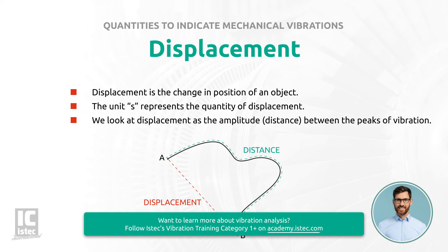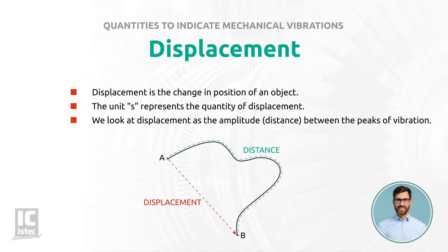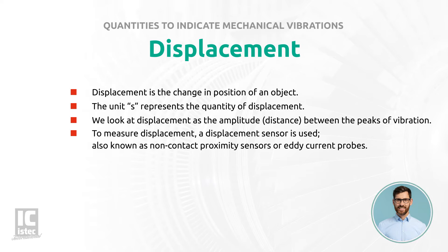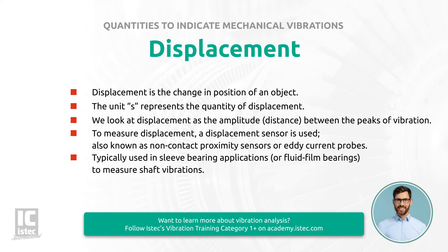We can see that both can be seen as a route from A to B, yet the distance is dependent on the route taken, whereas displacement is not. To measure vibration based on the displacement quantity, a displacement sensor is used. These sensors are also known as non-contact proximity sensors, or eddy current probes, and are typically used in sleeve bearing applications, or fluid film bearings, to measure shaft vibrations.